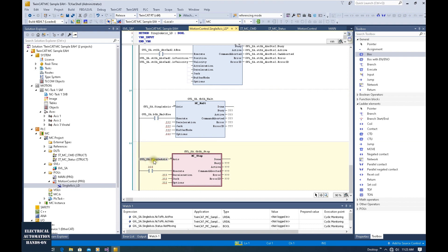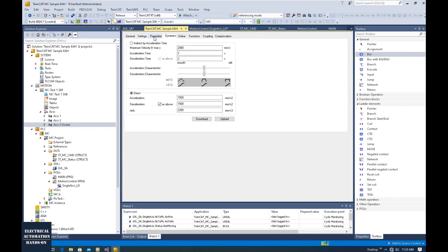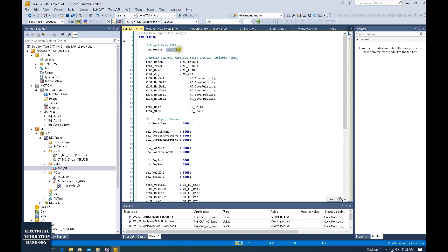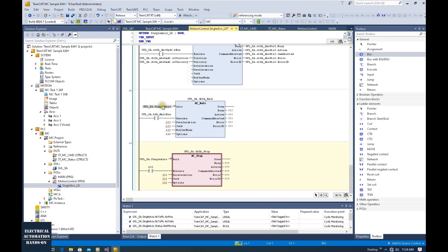This axis input is used to declare which axis this MC Stop will control. In the previous video, we are using Axis 3, which is one virtual axis. Inside the virtual axis setting, it is linked to the PLC variable named 'single_axis'. That variable is declared as an Axis_Reference REF. So using this way, this axis name links to the Axis 3 configuration. In our logic, we also use this name to say these function blocks are controlling this axis. So it links the function block with this axis configuration. Then comes the execute command.